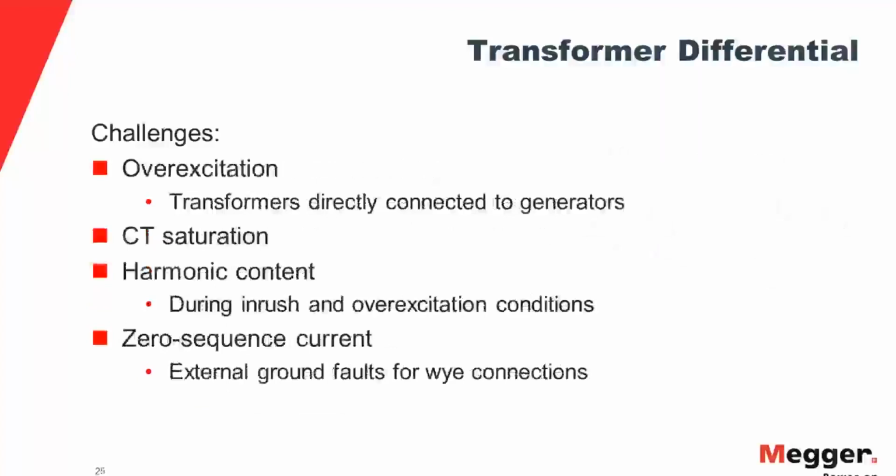That's only for a short duration, not for a prolonged period. Like the one shown here, your inrush current will be really high compared to the supplied voltage, but that's not forever. It has a decaying DC component as well, depending upon the DC constants of the system the transformer is connected to. So the inrush current will be really high.